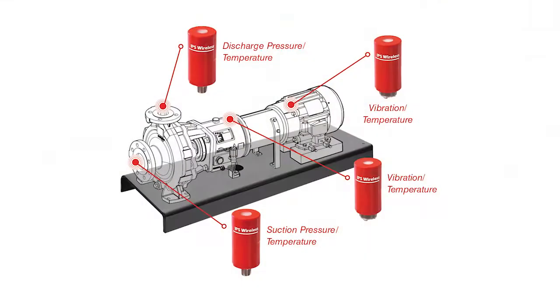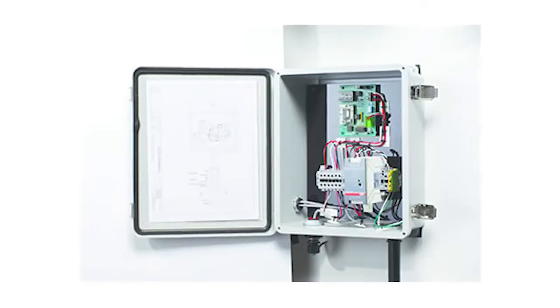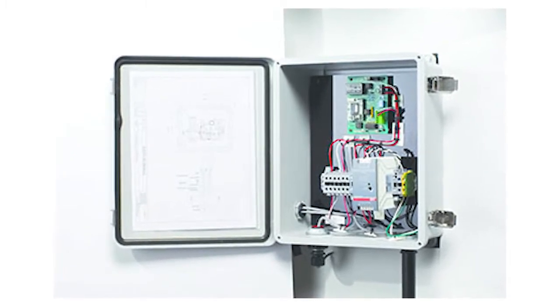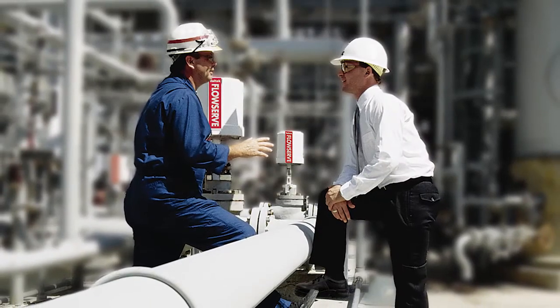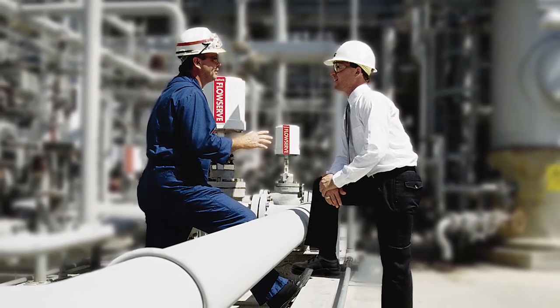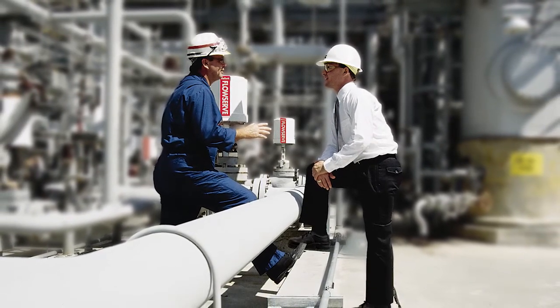One of the key security ingredients around the wireless FlowServe network is the unidirectional system. That simply means we have transmit-only devices and a receiver that receives data from those transmit-only devices, and we hold that data until the customer's operating system asks for that specific information, so all we can transfer across to the customer is the specific answers to the requests.